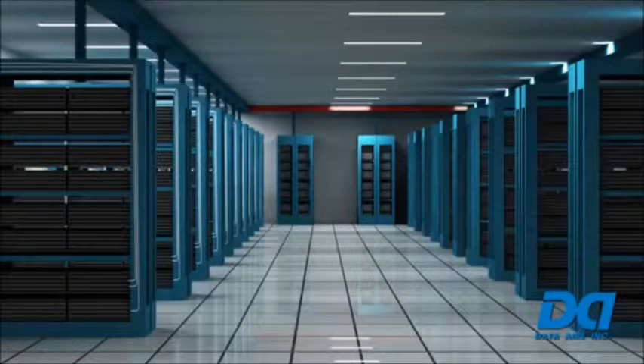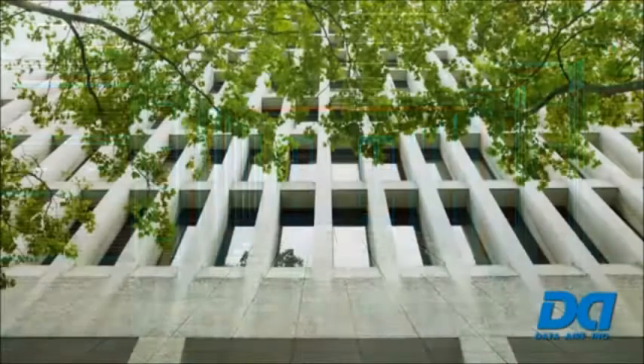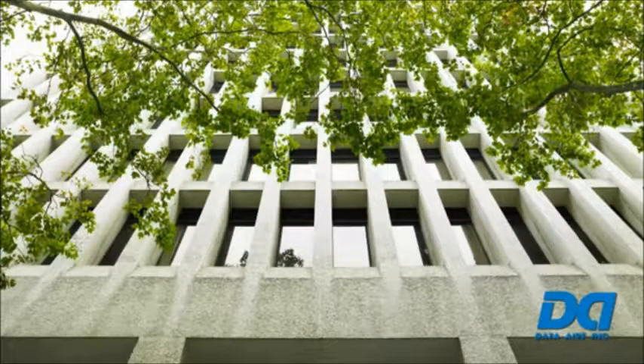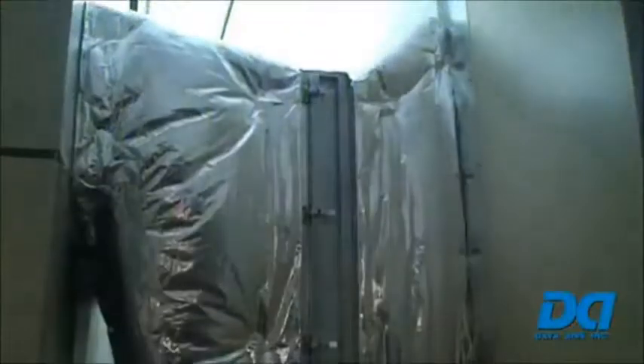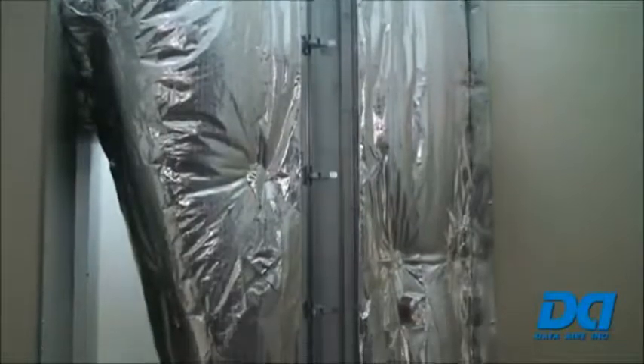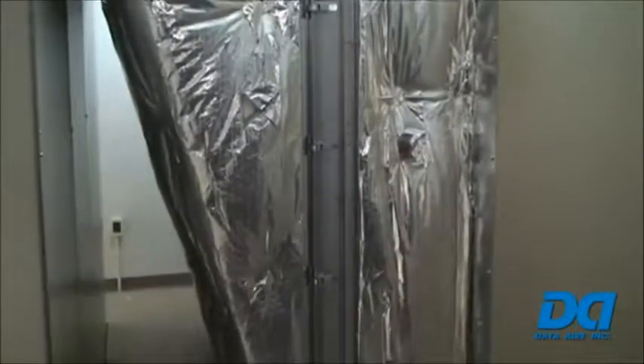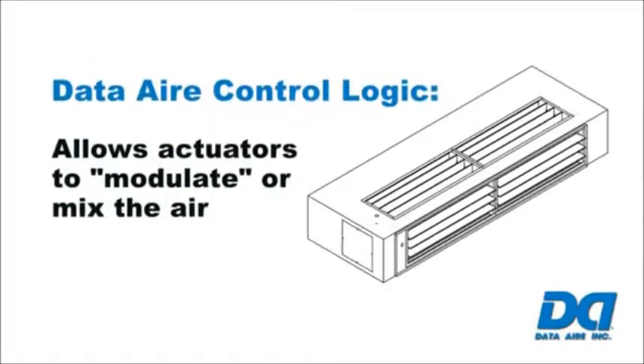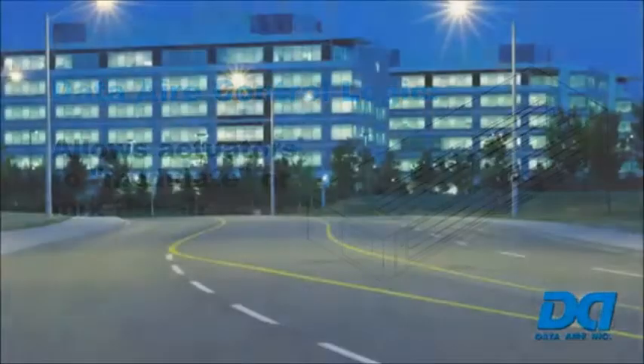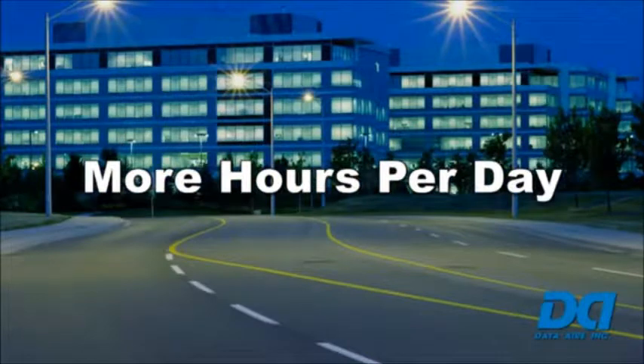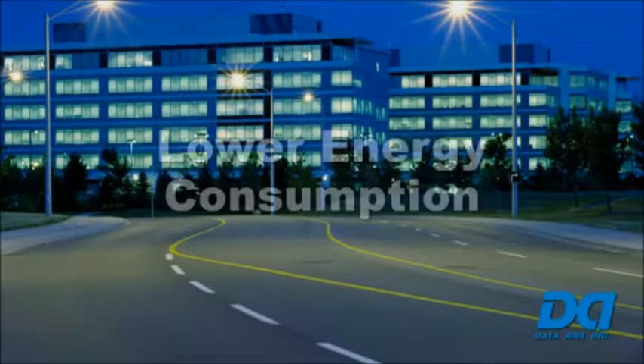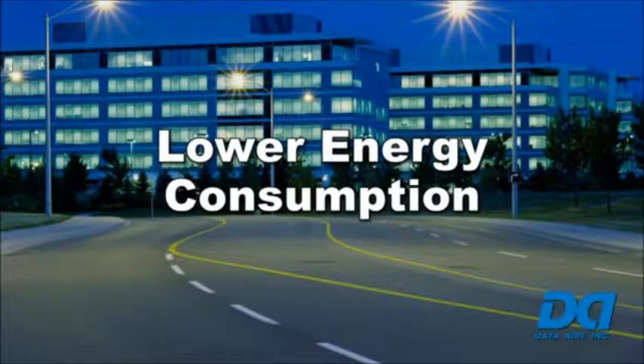Our control logic continuously measures both temperature and humidity in the data center space and compares that to the temperature and humidity of the outside air. Rather than terminating the use of outside air when it exceeds the set points, Data Aire's logic allows the actuators to modulate or mix the return and outside air. This continues until the conditions in the room reach the limits set by the data center. By doing this, the economizer can be used for more hours per day. The longer the economizer is used, the lower the energy consumption.